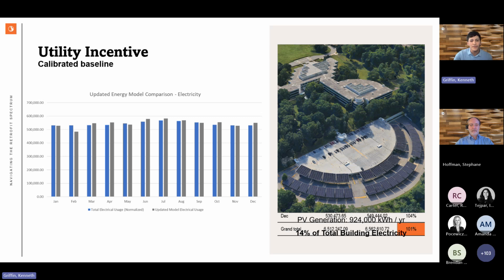We updated the model based on more current weather data. Before we had used TMY3 data, now we looked at previous years. Since this started in 2021 and no one was in the building in 2020 or 2021, we had to calibrate to 2019 data. That was different from what we'd been used to, since we'd normally average several years. Instead we used 2019, and also looked at 2018. We were able to get within 1% of calibrating our model for electricity. We also realized about 14% of the total building electricity was offset by their on-site PV generation.